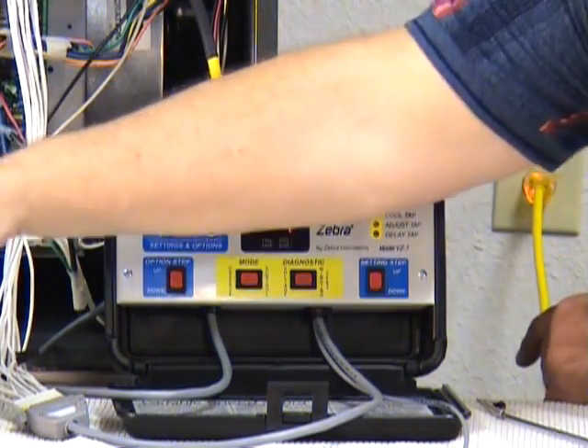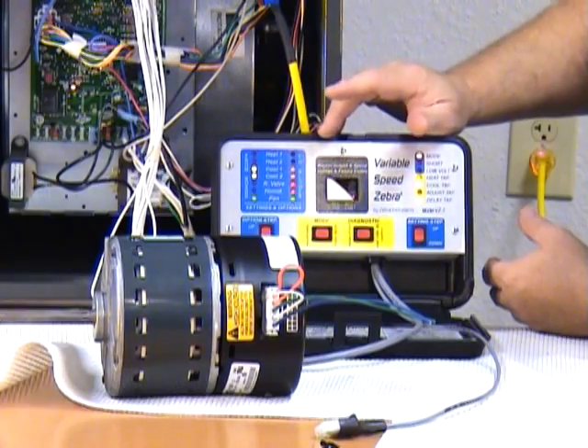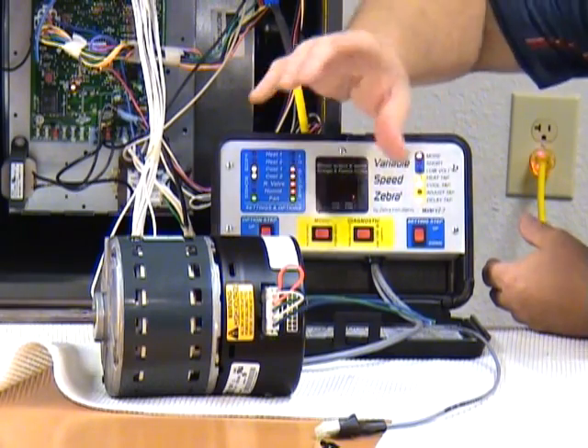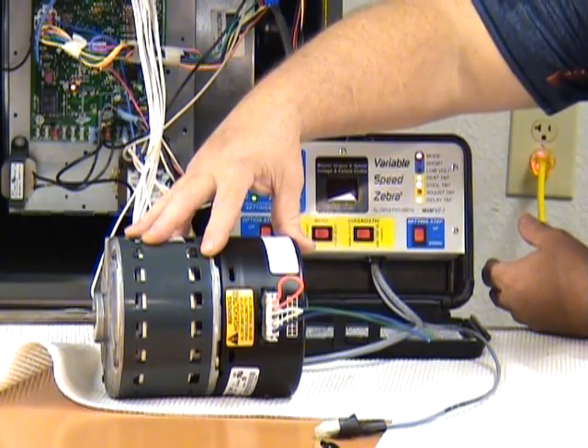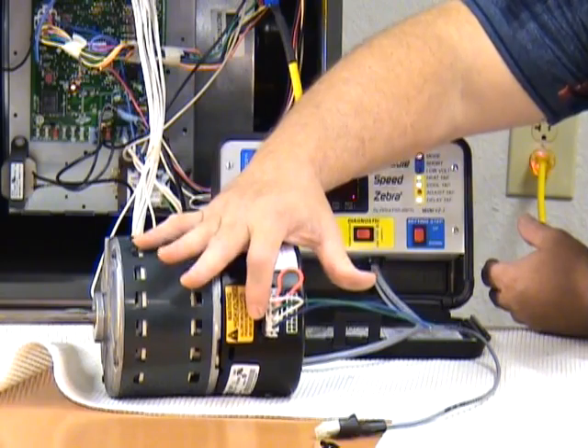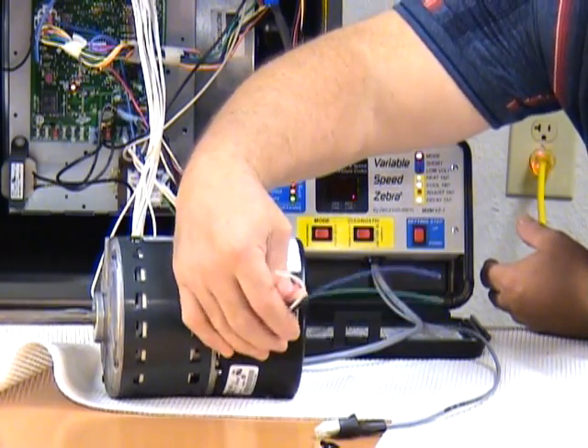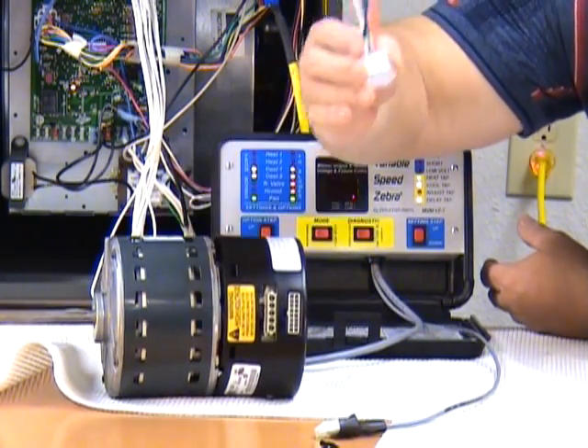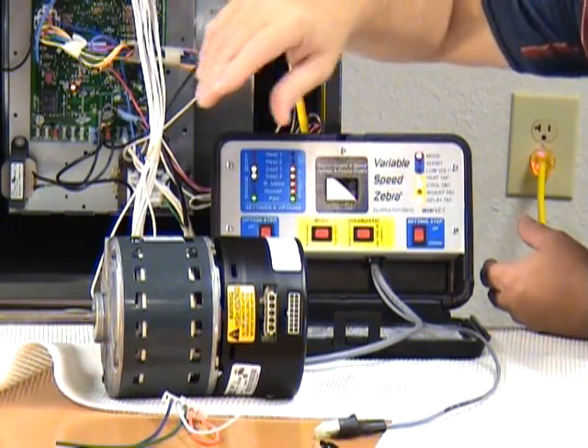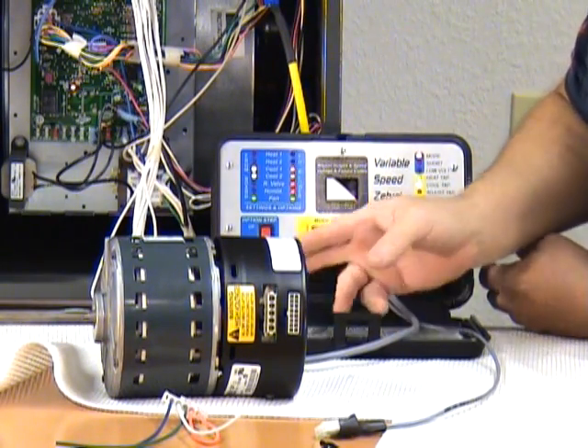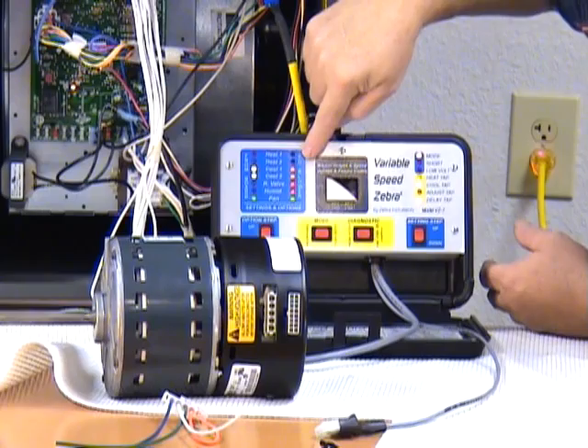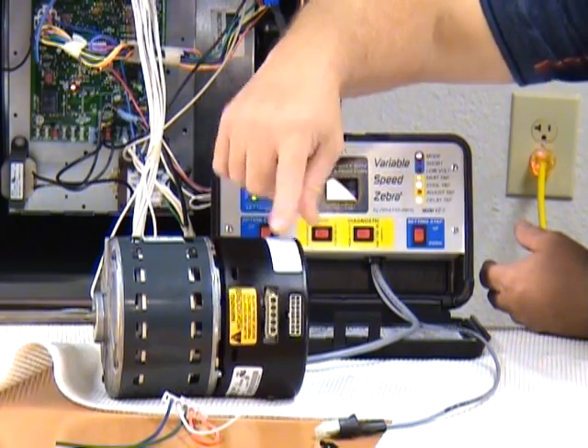Let's pull out a little bit. So at this point, we're thinking that we've got a problem inside of our motor. It's getting high voltage power. We've verified that by putting a voltmeter at these terminals on the high power harness, and we've verified that it's getting a signal going in on the signal harness.